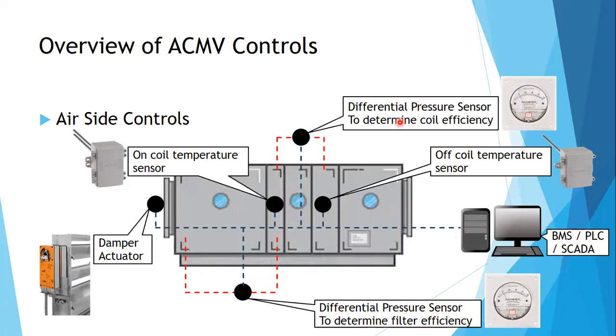Same with the coil differential pressure sensor. The before and after of the coil are being monitored, because not 100% of the particles are captured by the filter. Some of the particles are still within the air, and when it touches the cold, moist or wet coil, it gets stuck to the coil. So the coil becomes dirty and needs periodic cleaning. This differential pressure sensor before and after the coil will tell you when to clean the coil. So it also sends a signal to your BMS, telling, hey, this is the pressure drop of the coil. You need to clean already.